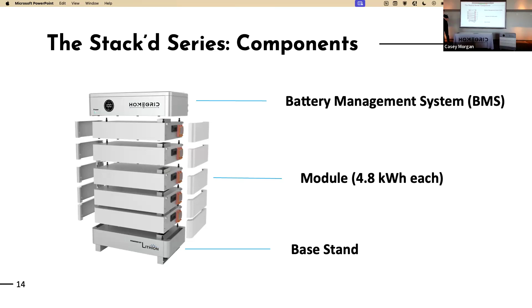Here's just a visual of all the configurations for a single stack and their kilowatt hours. One thing to note on these numbers - we do recommend, like I was talking about earlier, an 80% depth of discharge just to prolong the life of the battery, 85% is fine too. So when you sell this to your customer, understand you're selling them probably 80% of what is listed here, and you might want to add an extra module to account for that. Keep that in mind.